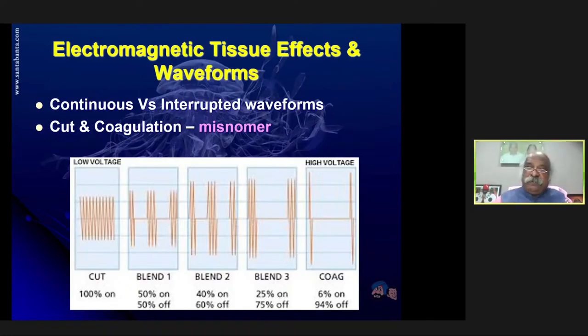Blend 1, 50% of the time it is on, 50% of the time it is off. Blend 2, 40% is on, 60% is off. Blend 3, 25% is on, and 75% is off. So as we increase the off time, the voltage gradually increases. So that is the difference between the waveforms, and the misnomer between the cut and the coagulation forms.